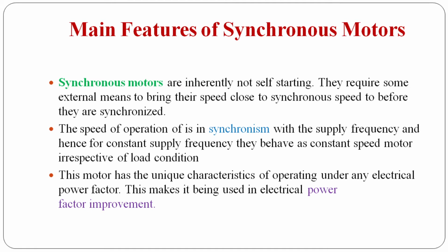What are the main features of synchronous motors? Now we are going to see that. Synchronous motors are not self-starting. This you have to remember, students. Synchronous motors are not self-starting. They require some external means to bring their speed close to synchronous speed. Because they work only on synchronous speed, they require some external starting device to bring their speed close to synchronous speed, before they are synchronized.